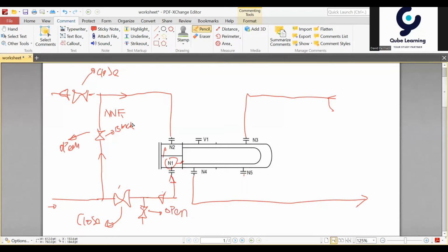So we have the backflush scenario on the P&ID, and we have to ensure that our P&ID addresses this backflush facility. In normal operation the bypass valve shall be in black color, because it is normally no flow. Okay, we'll go to the next topic.